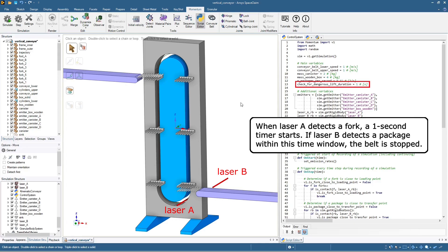Now, when laser A detects a fork, a one second timer starts. If laser B detects a package within this time window, the belt is stopped.